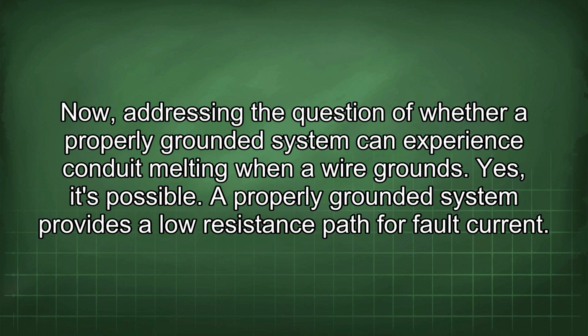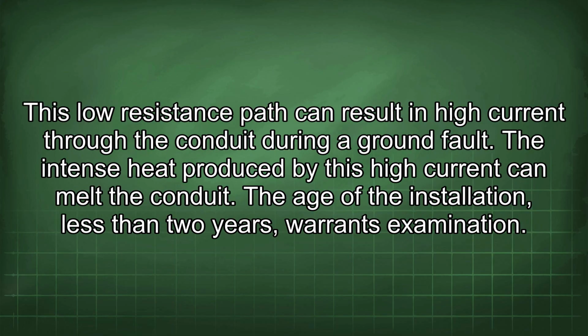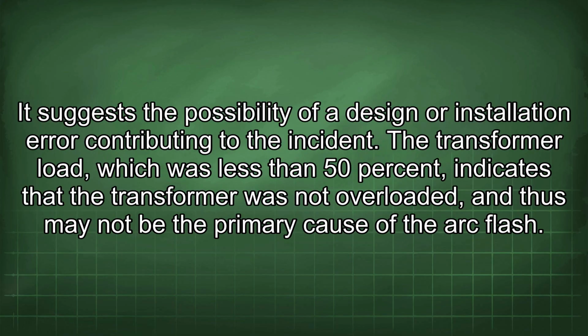Yes, it's possible. A properly grounded system provides a low resistance path for fault current. This low resistance path can result in high current through the conduit during a ground fault. The intense heat produced by this high current can melt the conduit. The age of the installation, less than 2 years, warrants examination. It suggests the possibility of a design or installation error contributing to the incident.